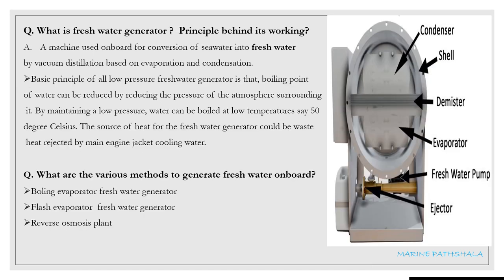The next question is: what is a fresh water generator and the principle behind its working? A fresh water generator is a machine used onboard for conversion of sea water into fresh water by vacuum distillation based on evaporation and condensation. The basic principle is that the boiling point of water can be reduced by reducing the pressure of the atmosphere surrounding it. By maintaining a low pressure, water can be boiled at low temperatures, say 50 degrees Celsius. The source of heat could be waste heat rejected by the main engine jacket cooling water.